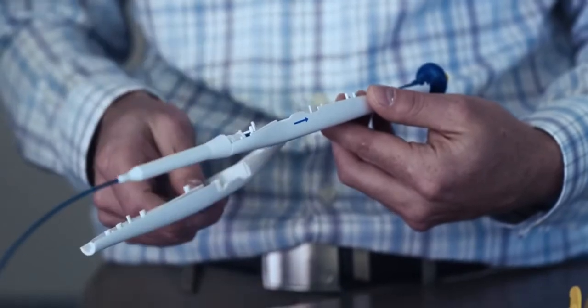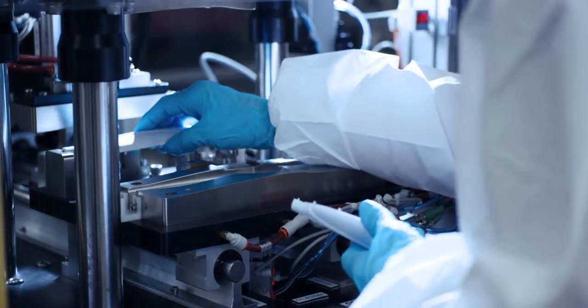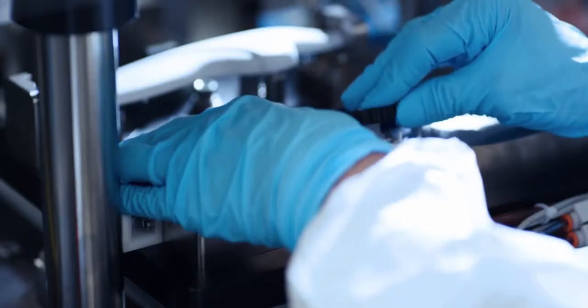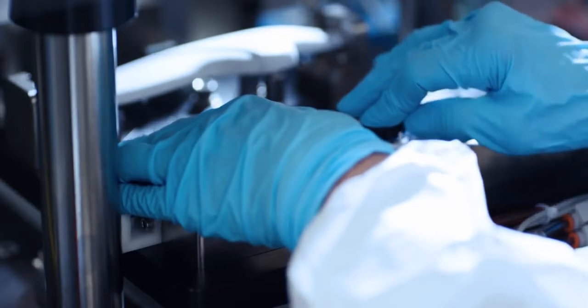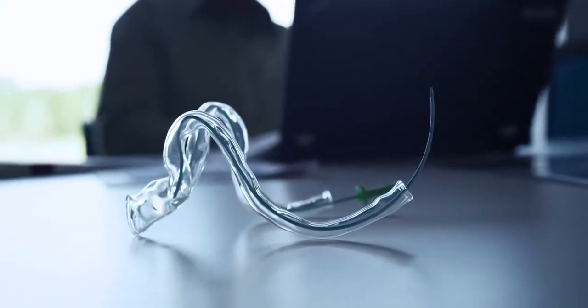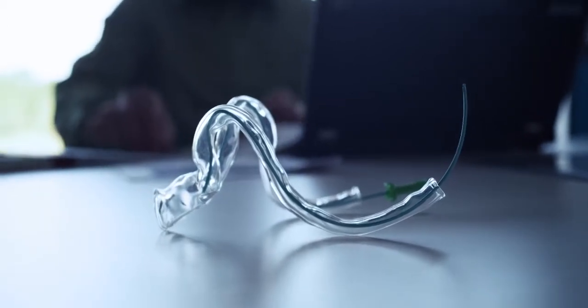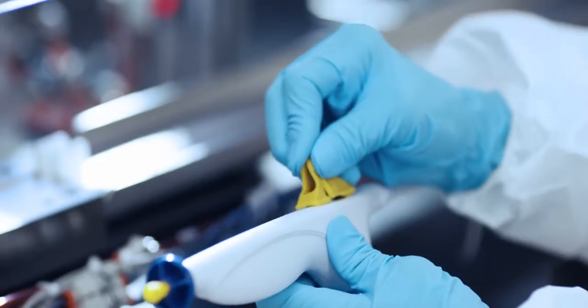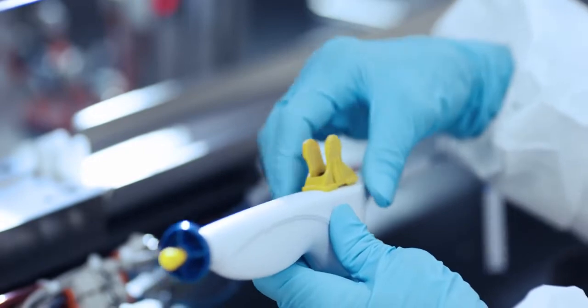Exploration and testing proved that a triaxial system would be an ideal platform to accurately deploy a stent in the SFA while simplifying the physician experience. The engineers designed this triaxial catheter system to be flexible enough to navigate tortuous anatomy with robust braided nylon shafts for stent deployment. The result is a delivery system with accurate deployment.